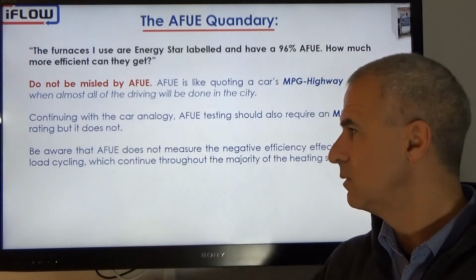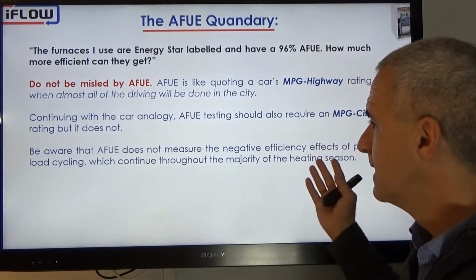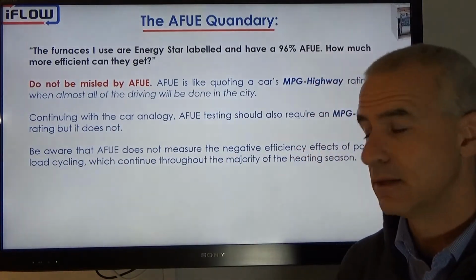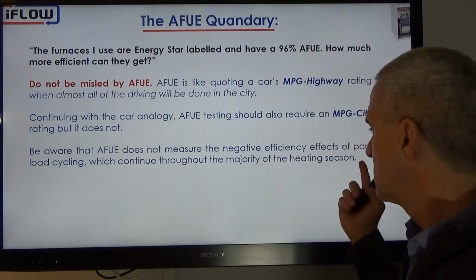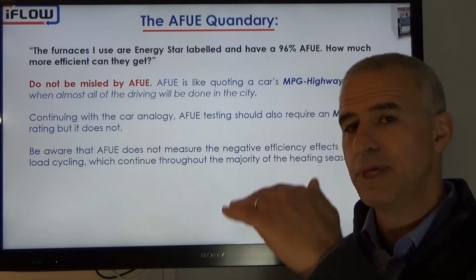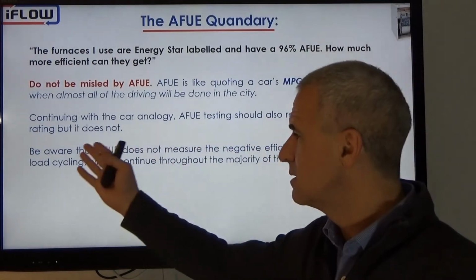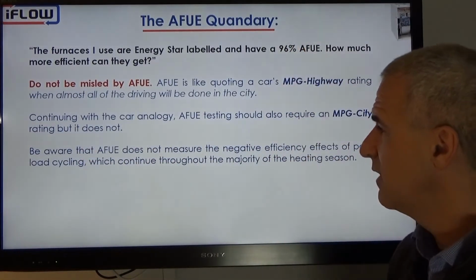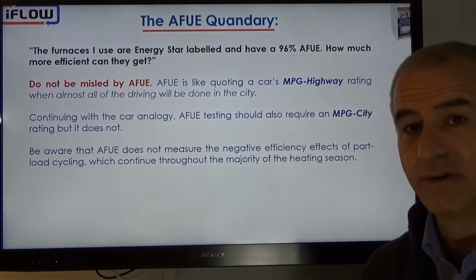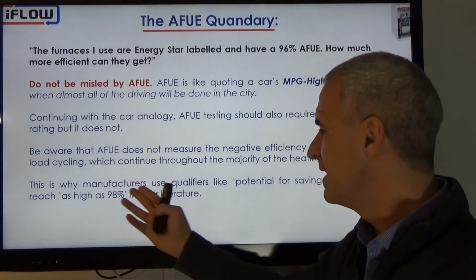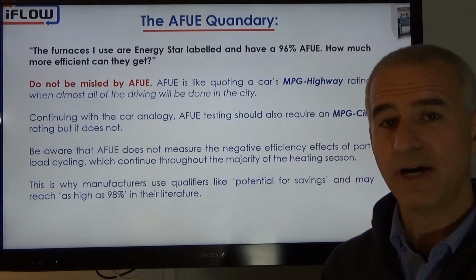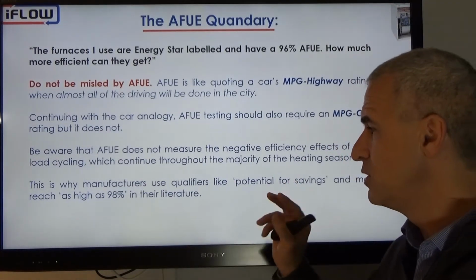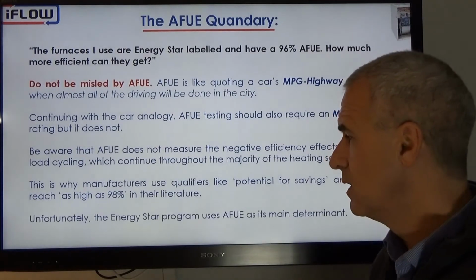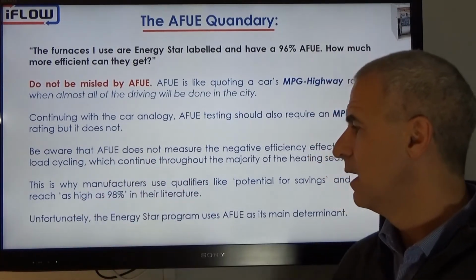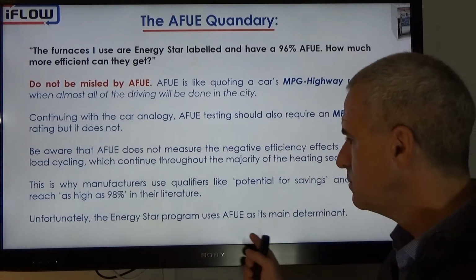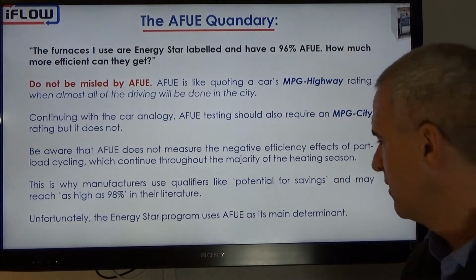So when we have to deal with those part load heating, and that's the majority of the heating season. It's only really when we're at the peak where we need maximum. The AFUE does not measure that. So the 96% or 95% that the AFUE quotes is really a fictitious number, unfortunately. And that's why many of the manufacturers use qualifiers like "as high as" or "the potential for savings," because they know it's not going to be operating at that rate much of the time if you actually measure it. But unfortunately, the Energy Star program uses the AFUE as its main determinant.